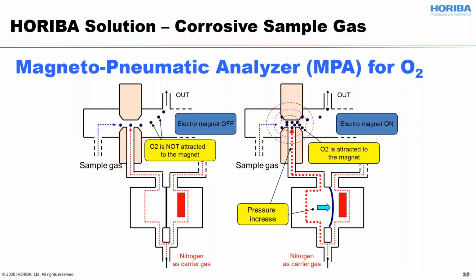As you can see, the beauty of this method is that the detector right here doesn't touch the sample, so it won't have any damage or corrosion from the sample gas, even if your sample gas may contain HF or HCl or Cl2, SO3. There's a lot of corrosive gas that could be included in the sample gas from an incinerator, but your detector doesn't touch that sample gas. There's no physical contact with it. So with that being said, magneto-pneumatic O2 analysis has great stability and a longer lifetime.